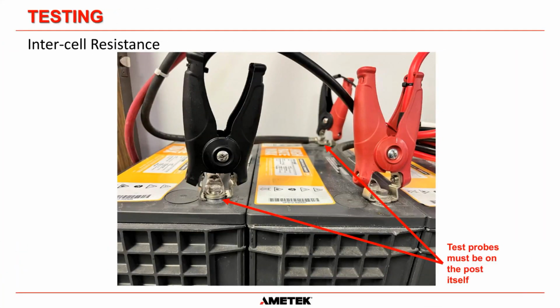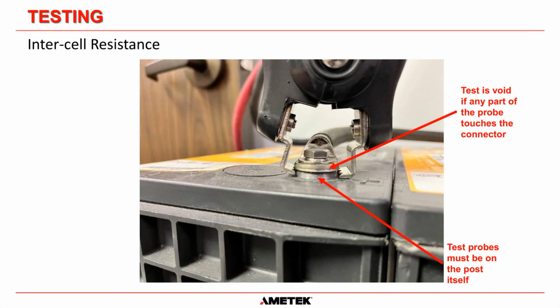So the test probes for the intercell connection must be on the post itself. You can see here, we're going to zoom in, that the jaws of these clamps are on the tin coated lead, or actually I think this is a lead post, directly onto the lead post. They're not connected to the lug or the cable in any way, shape or form. If we zoom in even closer, you can see the probe is only touching the post. It's not touching this lug part here, because if the probe touches this lug, then the test is void. It means nothing.